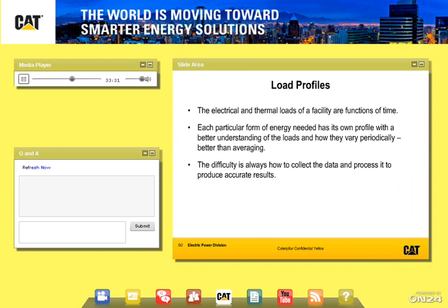The load profiles become very important in that you're going to have some issues with these systems, and you need to understand whether the profiles of the electric need and the thermal need are going to be coincidental or not. If they're not coincidental, then you need to be able to size your system based on the amount of heat I can get during my lower load on the generator sets and not expect to get 100% of the potential heat out of that system if, in fact, I'm not using electricity at that time. So understanding that can be very useful, and averaging both the heat and the jacket water, the electric load, is not a good thing to do. Being able to understand the profiles and when they occur and whether they're simultaneous or whether they're coincidental or not does make a difference.